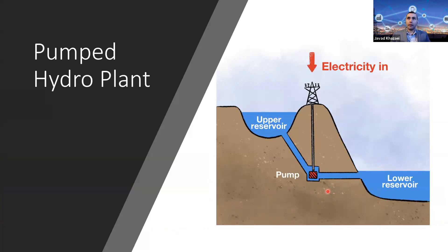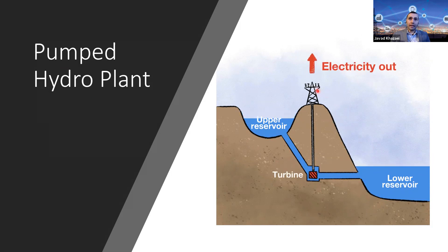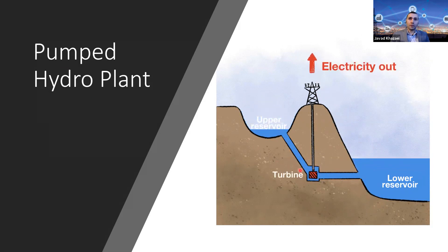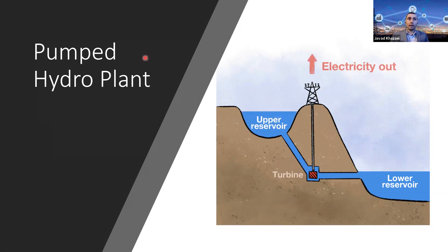Another hydro application is pumped hydro storage, using the elevation difference between an upper and lower reservoir. During the day, electricity pumps water from the lower to the upper reservoir. During the night when electricity is needed, the process reverses: water flows from the upper to the lower reservoir, rotating the pump shaft — now acting as a turbine — generating electricity sent to the system. This is a two-way energy system: consuming power one way, generating it the other. However, it is also slow because of its reliance on water flow.